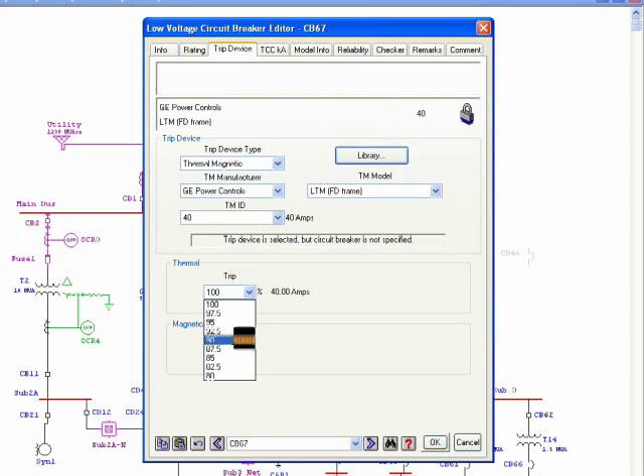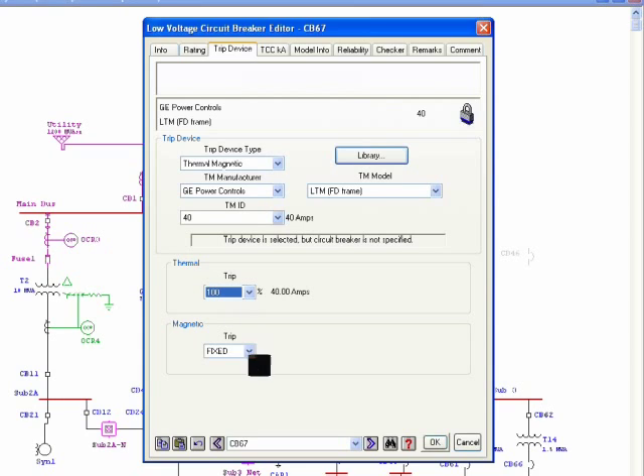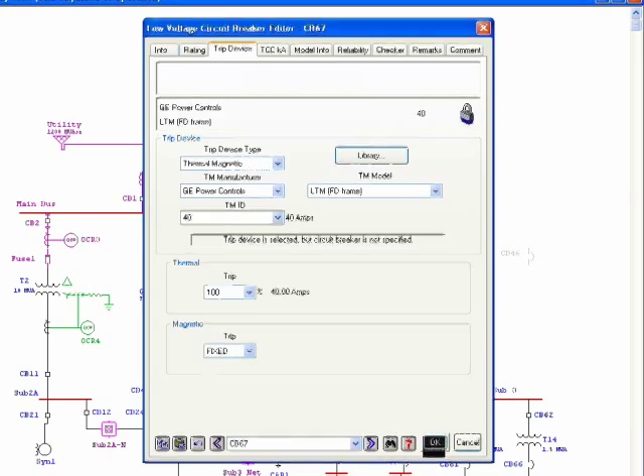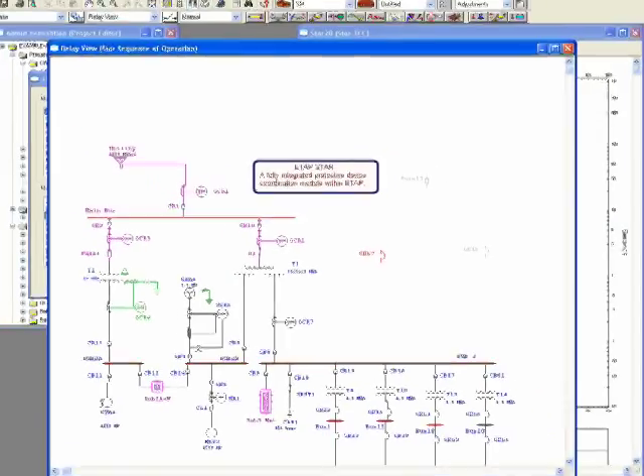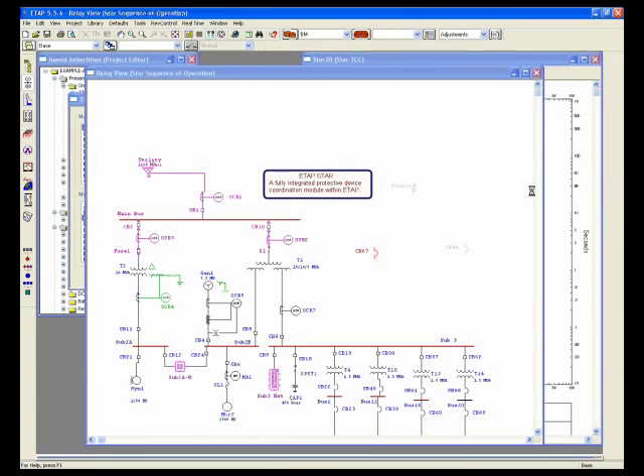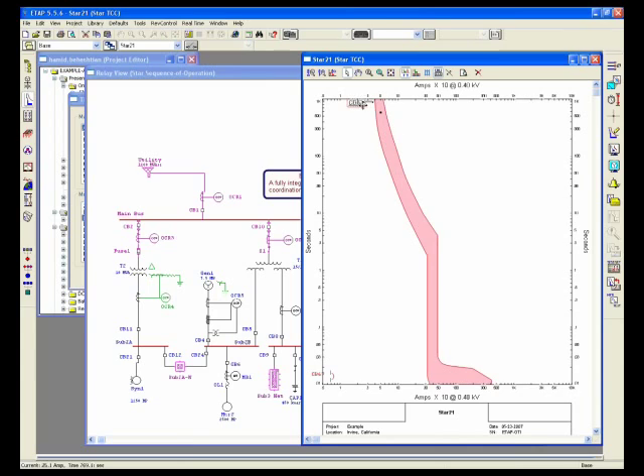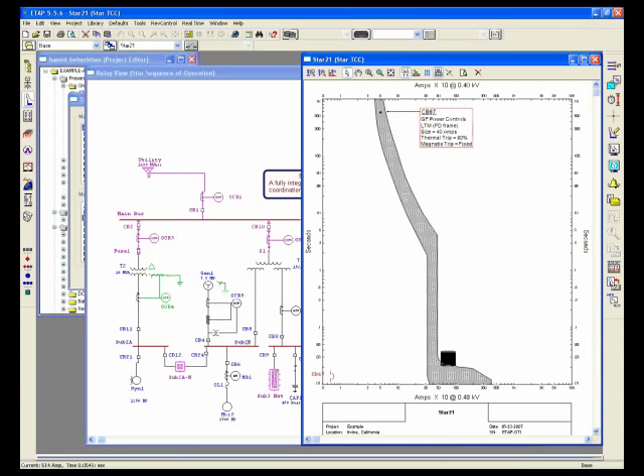I can change my thermal section by changing this setting, and the magnetic for this case is fixed. So if I take a look at this curve, it shows like this. I can shift my thermal section to the left and right without changing my instantaneous portion.